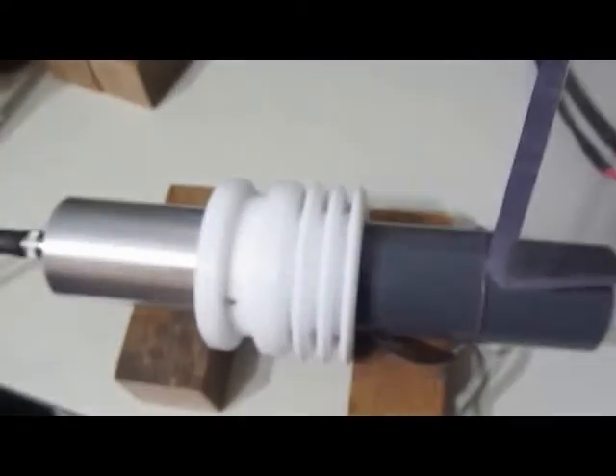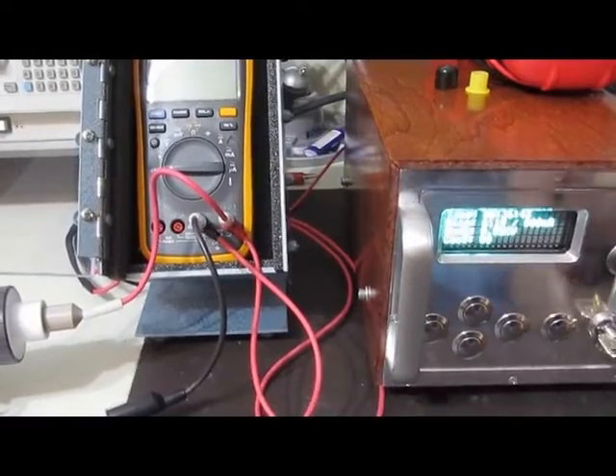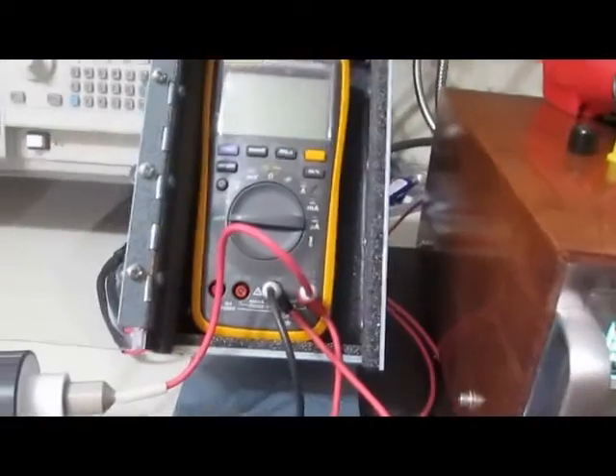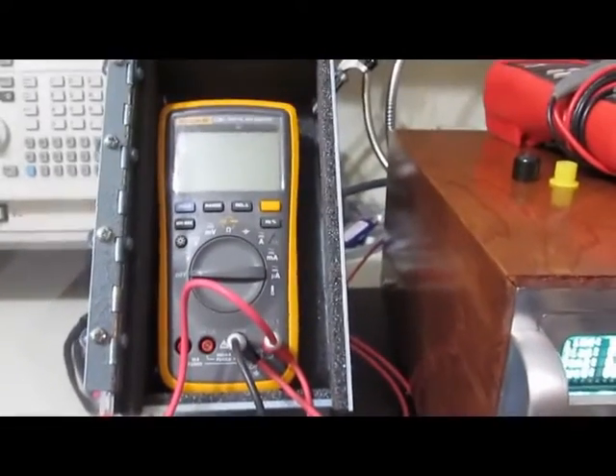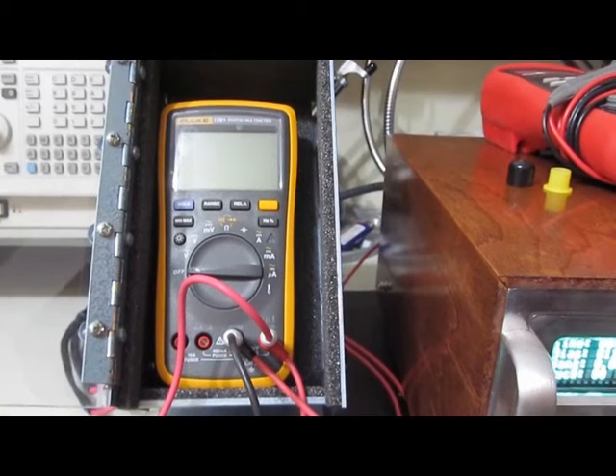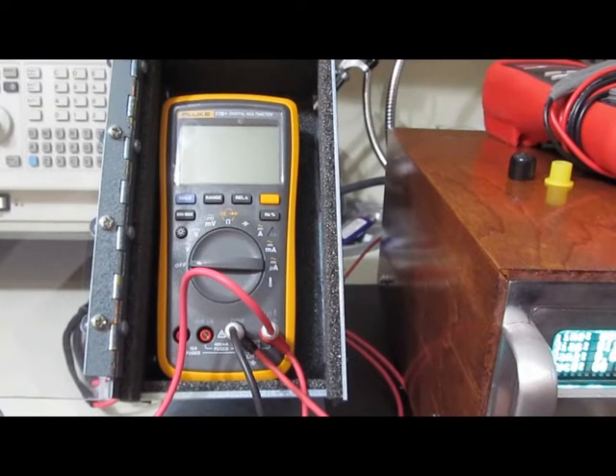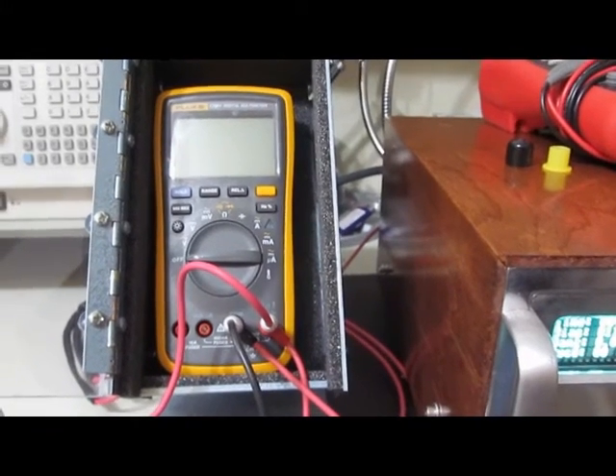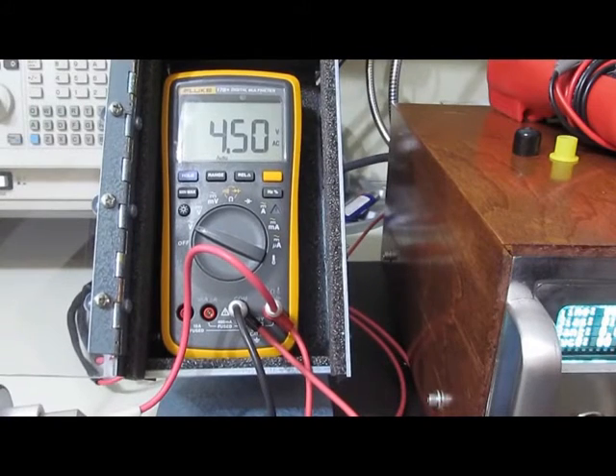So I plugged the generator into the little distribution block here, and I'm going to be using this other set of cables. This is just an easier way for me to monitor with a high voltage probe. So if something does break down, if I'm monitoring with the scope, I can usually detect that pretty quick. So again, this is roughly 5.9 kV and about 100 microsecond full width to half height. Should be good to go.